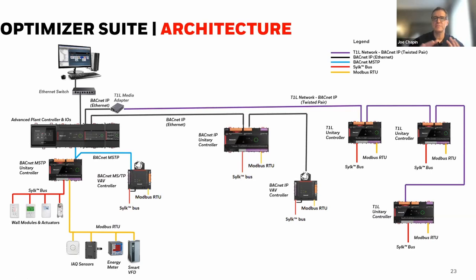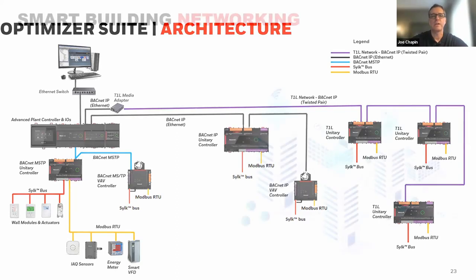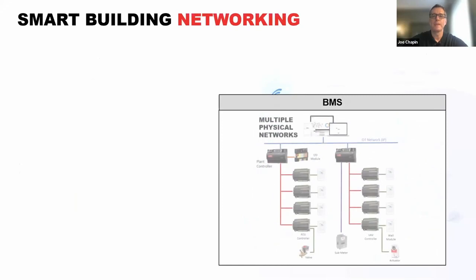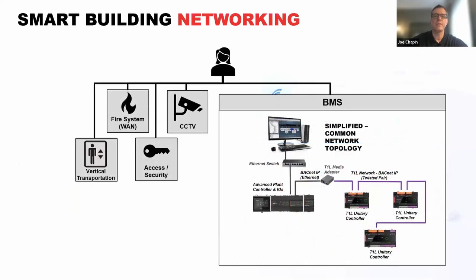What this does is simplify your network architecture. The backbones are T1L or BACnet IP. All the devices downstream of the controllers, depending on what the communication method is, you have all the flexibility that you want to bring it into one device and backhaul it up to the BACnet IP device via T1L or your category 5 cabling. So a lot of things you can do here. So in this case, what this is showing you, I have multiple different networks to start with. I implement the optimizer and I simplify the network.